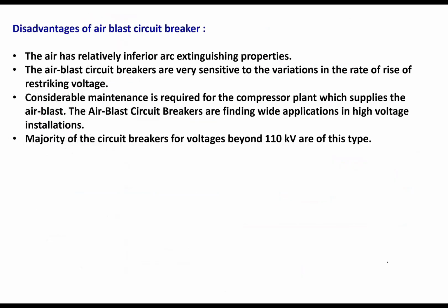Disadvantages of air blast circuit breakers. Again, what is the medium? Air. The dielectric strength of air is less when compared to other media like vacuum, sulfur hexafluoride, or oil. Understand? So air blast circuit breakers are very much sensitive to the rate of rise of restriking voltage. That is one more disadvantage. If the rate of rise of restriking voltage is more, then what will happen? The arc will repeatedly start reappearing. So again, we have to repeatedly operate the air blast circuit breaker.